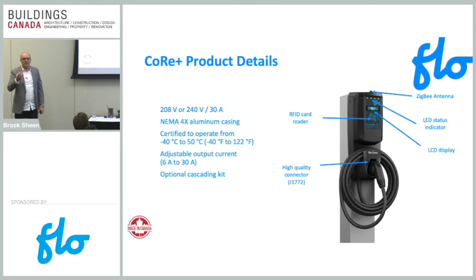That's from basically heat buildup over time, and the resistors are just basically loosening up, kind of like a spring does over time. Same thing happens in those. There's a hell of a lot more heat going on in these connectors, right? So you start typically seeing failures at 500 to 2500 sessions in those connectors. Our connectors are rated for over 10,000 sessions. So again, a significant change.